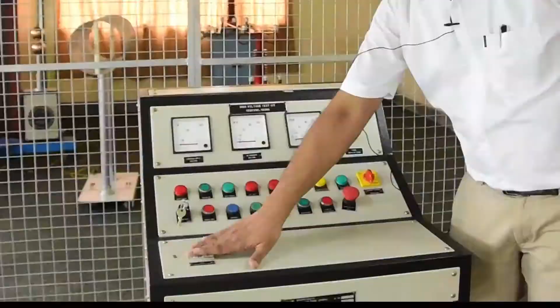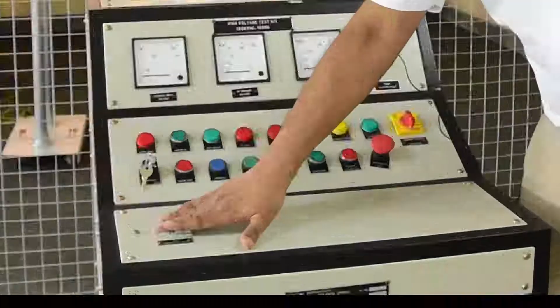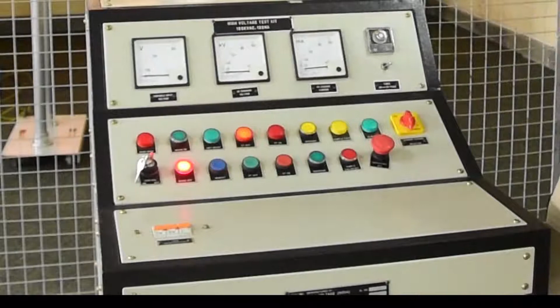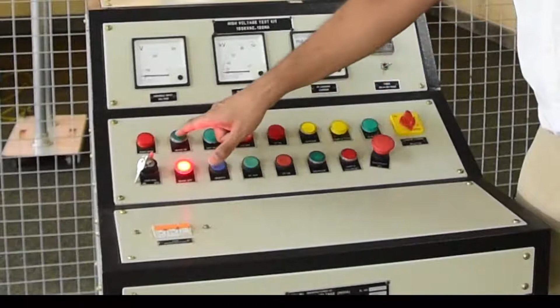Let me now switch on the supply. So I'll put the main MCB on. Right, and then I put this key input on, ensuring that the corona cage is closed and there is no one inside the cage, which safety measures must be observed. Please note that the procedure is the same. The left hand side is the mains control, here in the middle there is the HT control, and on the right hand side there are the voltage control switches. That procedure is very similar to the sphere gap assembly. Now I'll put the mains on, so it shows unit ready and HT is off, so I'll put HT on. This indication now shows that the high voltage is available for application across the cage, and now I go for increasing the voltage while observing the voltage here on the panel.